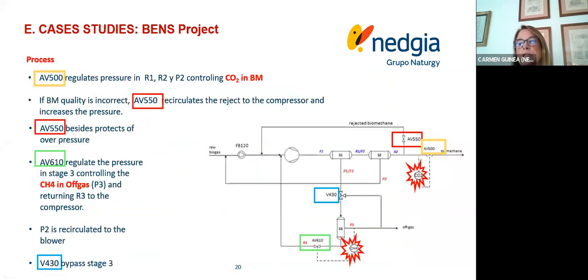The upgrading process in this plant is controlled by the concentration of CO2 in the biomethane. The goal is to obtain CO2 below 2% by regulating the control valves. If valve 500 closes, the biogas compressor increases the discharge pressure, looking to obtain the objective of 2% CO2. If the quality of the biomethane does not comply with the required quality, valve 550 would open and send the biomethane back to the suction of the compressor, increasing the pressure.